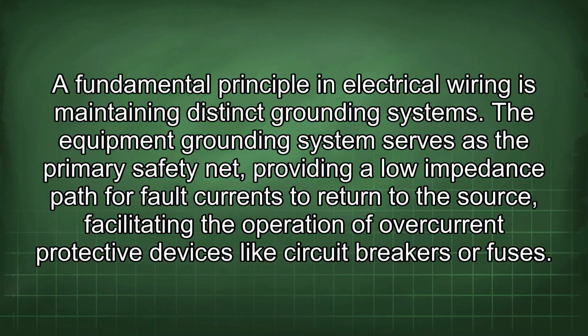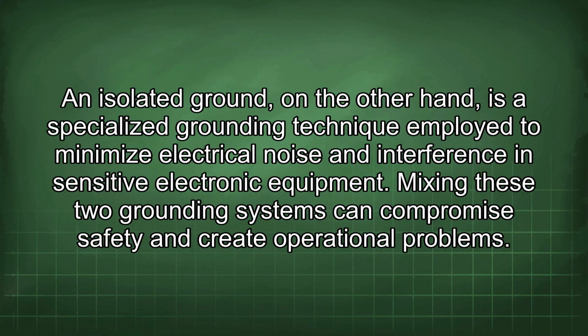A fundamental principle in electrical wiring is maintaining distinct grounding systems. The equipment grounding system serves as the primary safety net, providing a low impedance path for fault currents to return to the source, facilitating the operation of overcurrent protective devices like circuit breakers or fuses. An isolated ground, on the other hand, is a specialized grounding technique employed to minimize electrical noise and interference in sensitive electronic equipment. Mixing these two grounding systems can compromise safety and create operational problems.